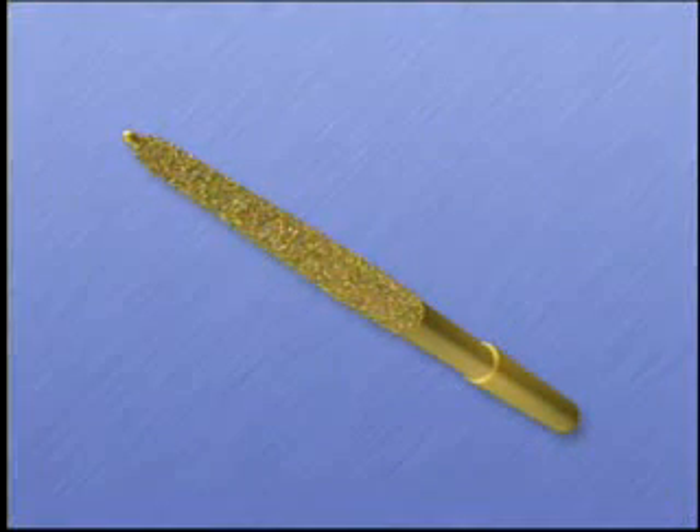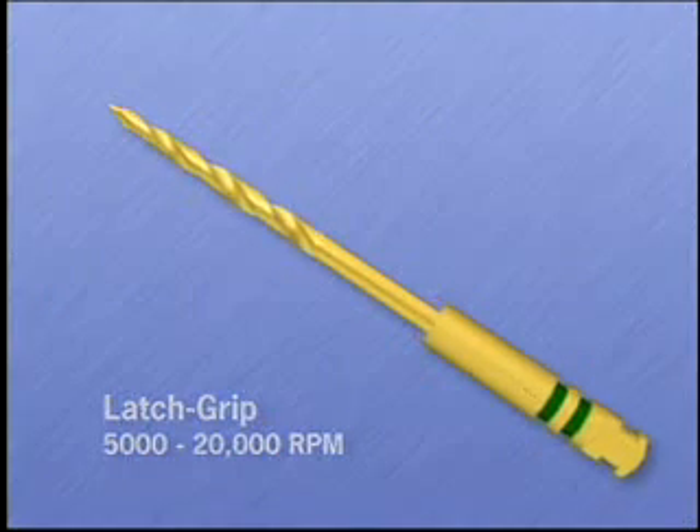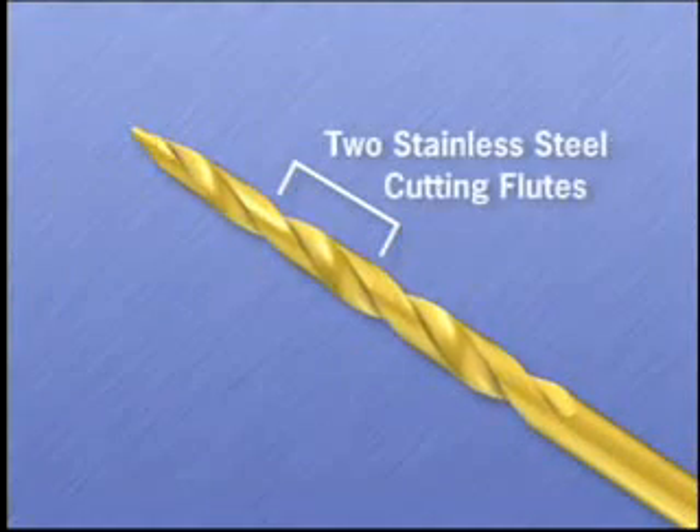The LA Axxess burs with a latch grip design are intended for use in standard slow speed handpieces at 5,000 to 20,000 RPM. They have two non-landed stainless steel flutes for aggressive side cutting in dentin.